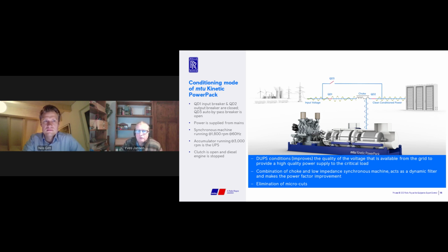Now, let's talk about the single line of the MTU kinetic power pack. The unit works in combination with a switchgear, the power panel or the POP. It is equipped with one input circuit breaker, the QD1, one output circuit breaker, the QD2, and one automatic bypass switch, the QD3. It also includes a choke, or reactor as we could also name it, that makes the segregation between the input, where the grid is connected, and the output, where the critical load is connected. The synchronous machine is electrically connected at the end of the choke.